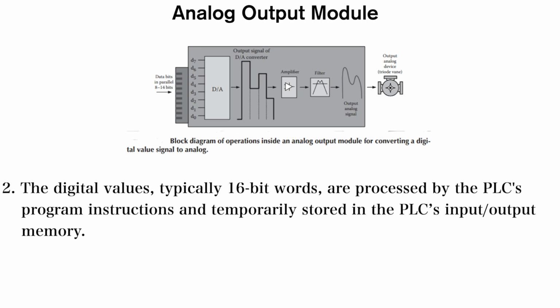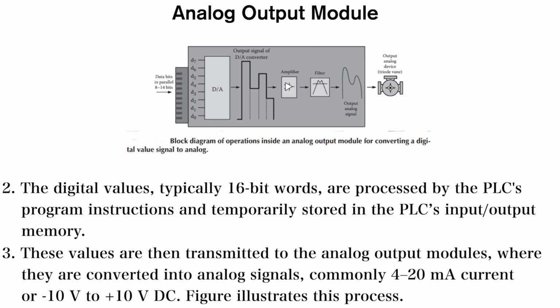The digital values, typically 16-bit words, are processed by the programmable logic controller's program instructions and are temporarily stored in the PLC's input and output memory. These values are then transmitted to the analog output modules, where they are converted into analog signals, which are commonly 4 to 20 milliampere current or range from minus 10 volt to plus 10 volt DC. This figure illustrates the process, and you can clearly see the conversion.